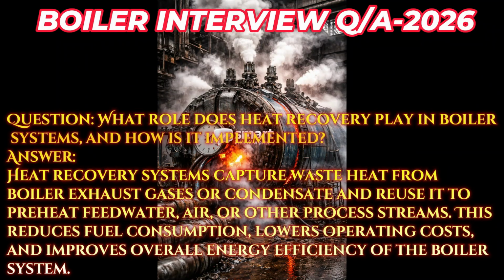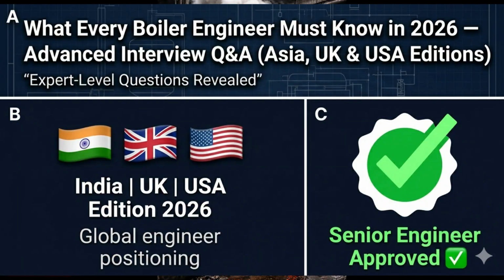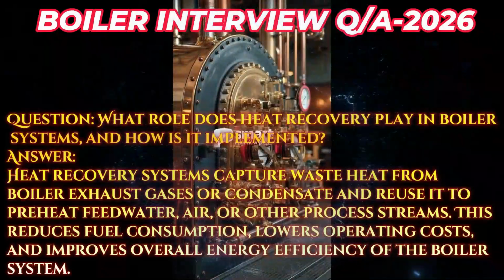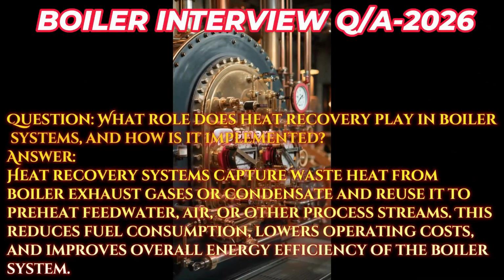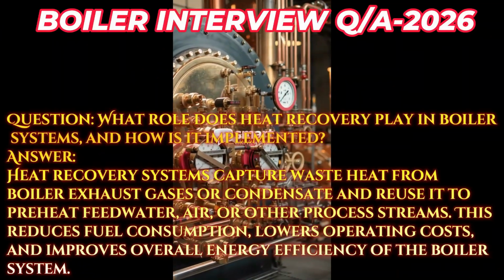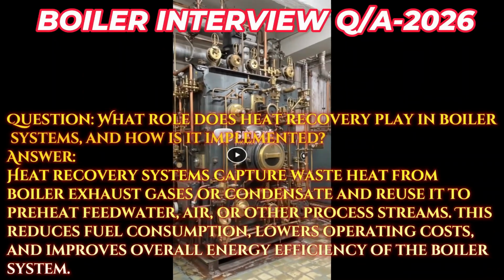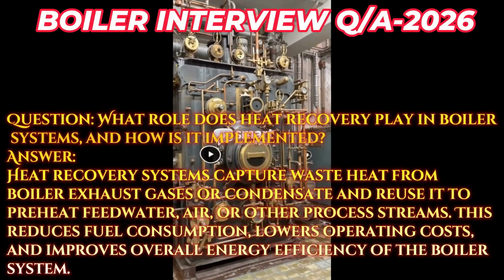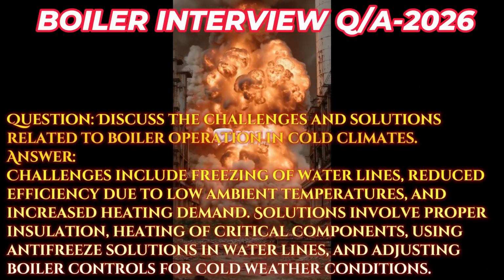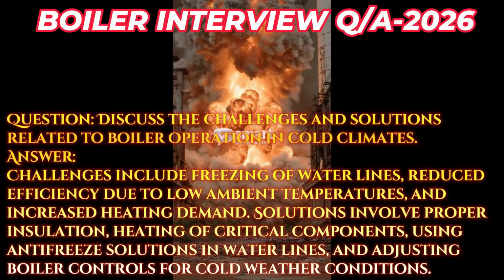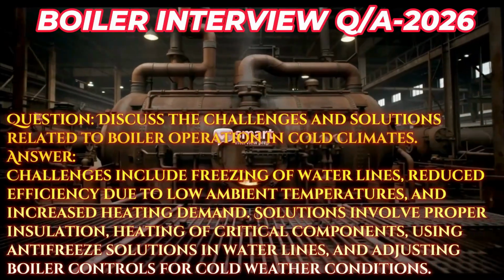Answer: heat recovery systems capture waste heat from boiler exhaust gases or condensate and reuse it to preheat feedwater, air, or other process streams. This reduces fuel consumption, lowers operating costs, and improves overall energy efficiency of the boiler system. Question: discuss the challenges and solutions related to boiler operation in cold climates.